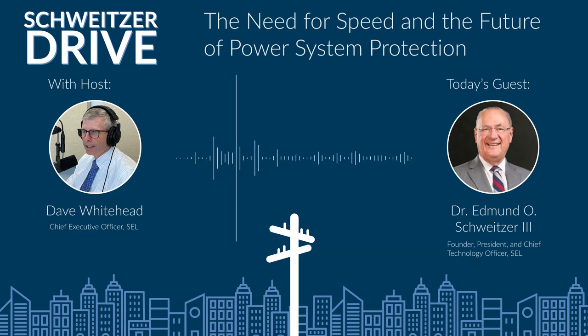Excellent. And we've got to remember that faults are dangerous, destructive, and disruptive. It's an unintended act of welding out in a transmission line that's damaging the surfaces of insulators and melting conductors. And the amount of energy is proportional to the square of the current through the fault times the duration of the fault. So the quicker we can clear the fault, the less danger and destruction there is. So the simplest answer is the shorter the better.